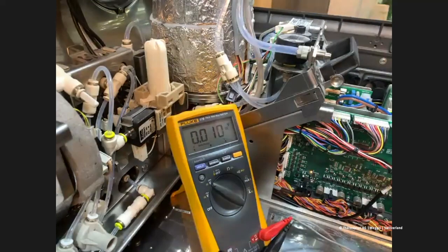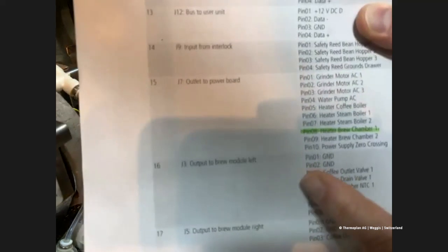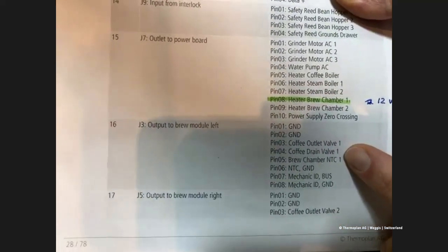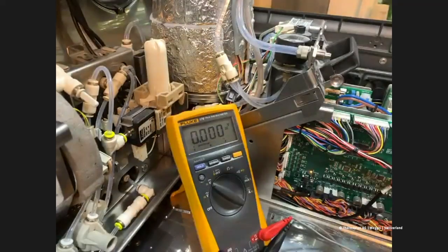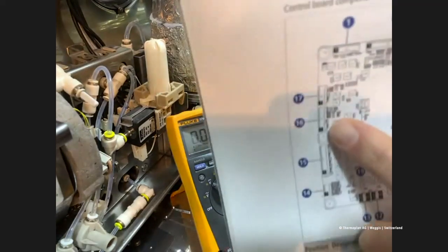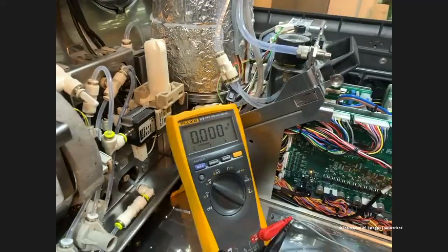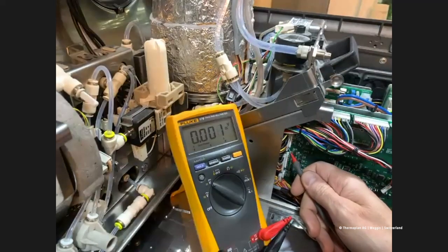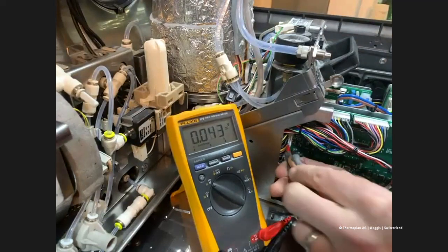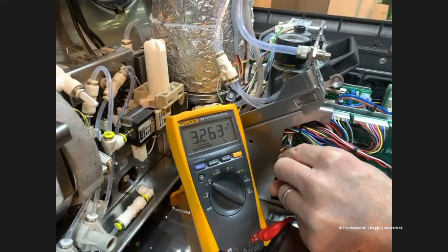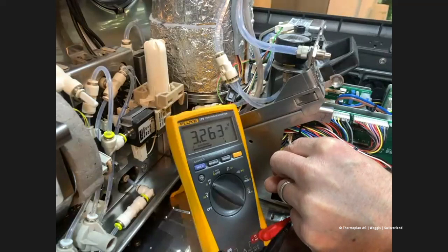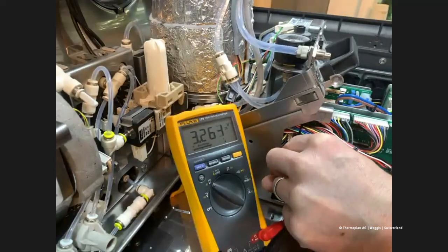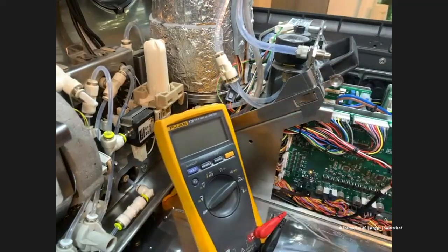Now, the other thing we could test, or look at, is number 16, which is our output to brew module left, because it has our brew chamber heater NTC and the NTC ground. So we're looking at connector 16, again starting at 1, and we want pins 5 and 6. Let's count: 1, 2, 3, 4, 5, it's the yellow wire, 6 is black. We should get our 3.3 volts DC. If we aren't getting voltage there, that means our CCB isn't sending a signal to the NTC.